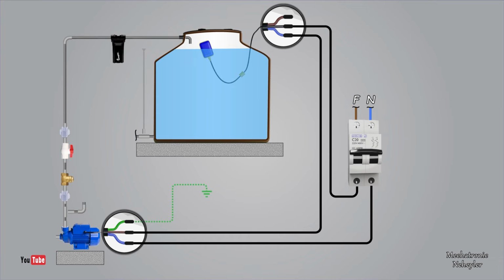Although all this wiring and connection seems correct and works, there is actually an observation here. The float is connected to the same circuit as the electric pump, that is, a lot of current will be circulating through them, as well as a high voltage. For example, where I live, we use a supply voltage of 220 volts between phase and neutral, and that voltage would also be present in the floats. According to the IEC standard and various regulations from different countries, they maintain that the power supply for devices operating in humid or wet locations must be no more than 24 volts.